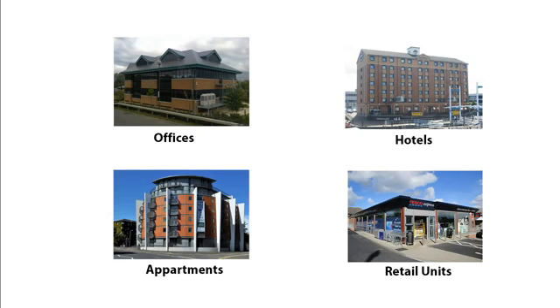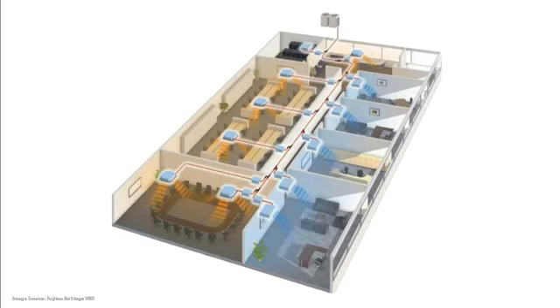As some of these units can provide heating and cooling, they save precious space within a building, so you might not need an additional boiler or chiller, and obviously it takes up a lot less room compared to multiple split units or a multi-unit. They are, however, quite expensive to install, and that's because of all the controls equipment and pipe work. And we'll see in some of the later videos the amount of controls and equipment that are installed in these, and you can get an idea of why these cost so much to install. So although the initial installation cost is fairly high, the actual operating cost is going to be much lower.